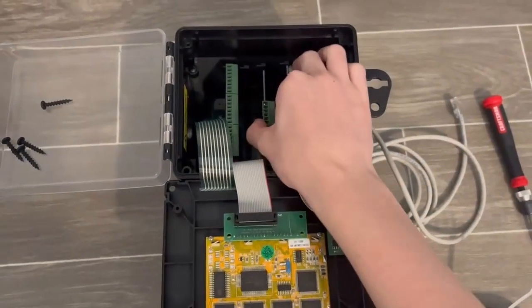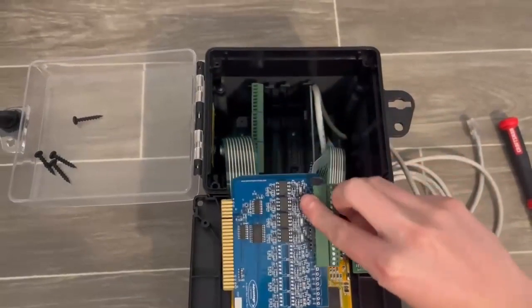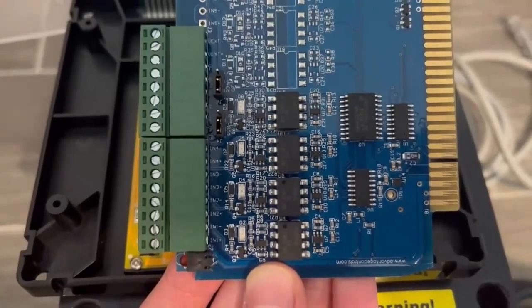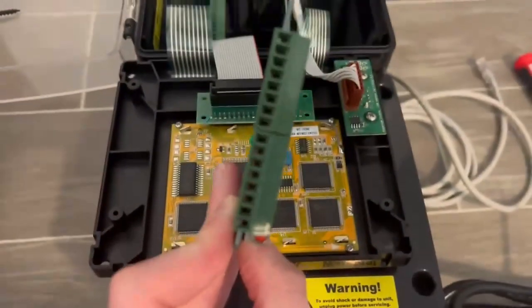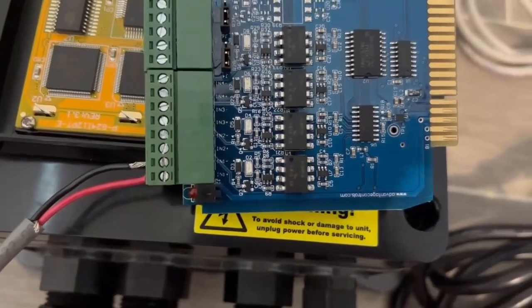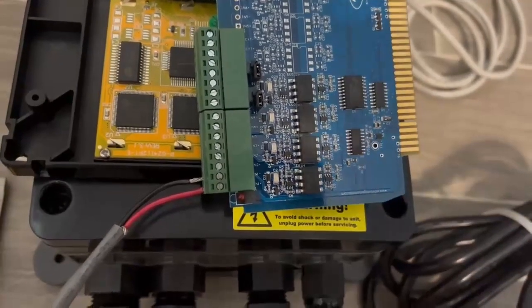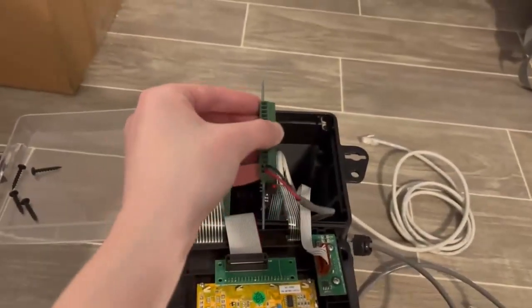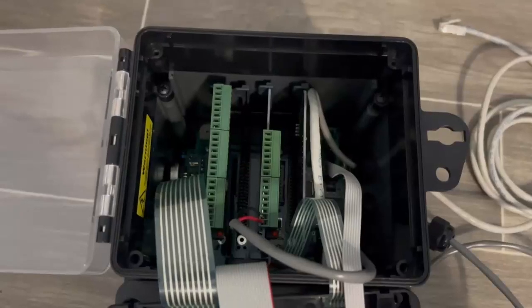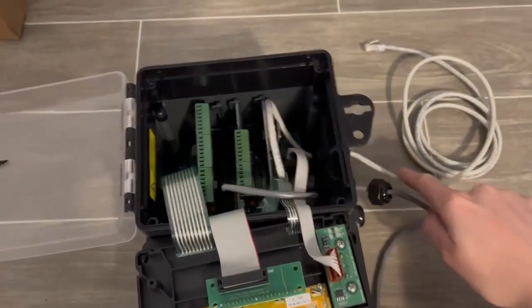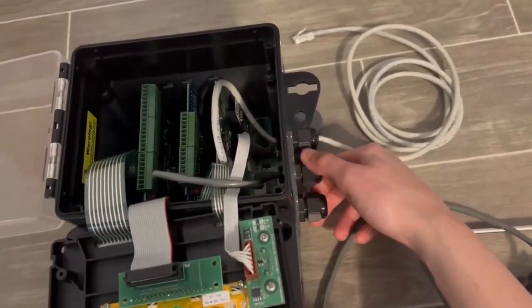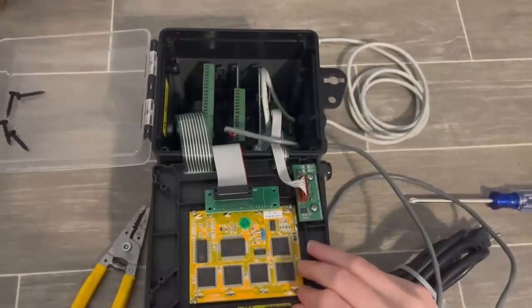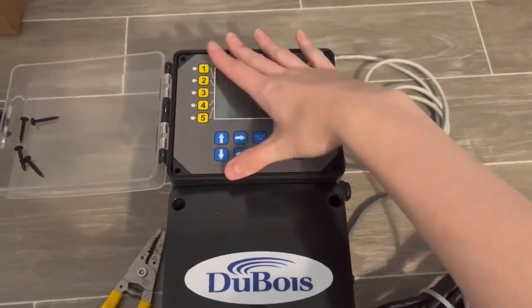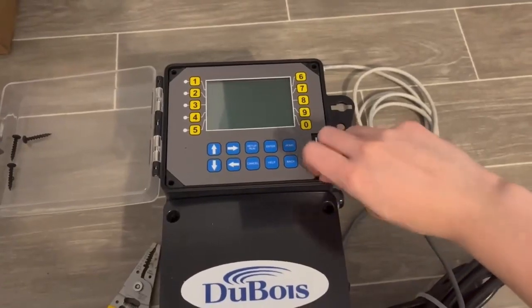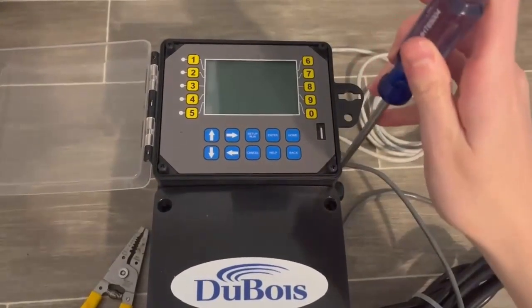Next, remove the middle plate inside of the monitor, as seen here. Find where it says ion 1 plus and minus on the plate, and then find the corresponding wiring boxes. Place the ends of the stripped wire into the corresponding places in the wiring box, positive going with red, negative going with black. Secure with the small flathead. Insert the plate back into its original spot inside of the monitor. Pull the wire from the outside to make it taut, and then screw the black knob back into place, securing the wire. Put the front screen back into place, and then insert the screws back into place as well. Tighten the screws with a Phillips head screwdriver.